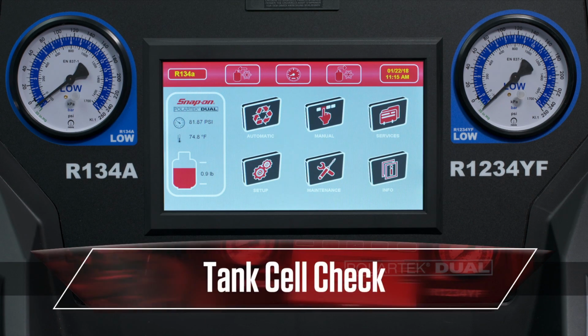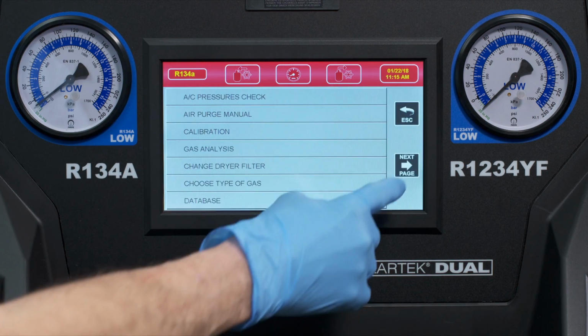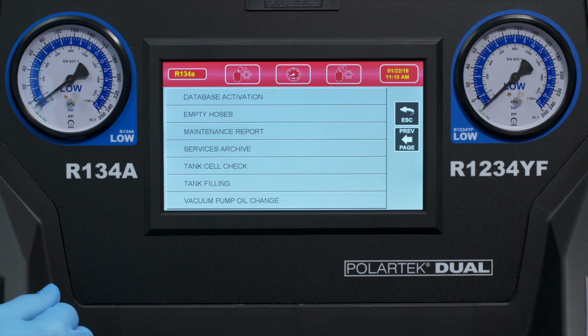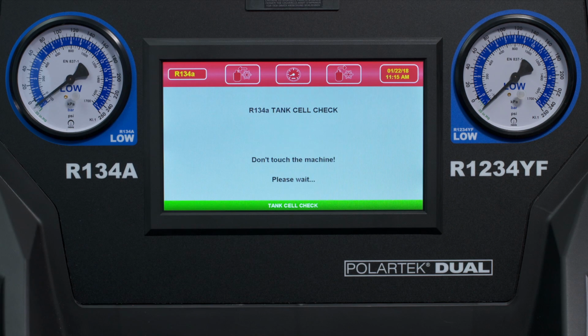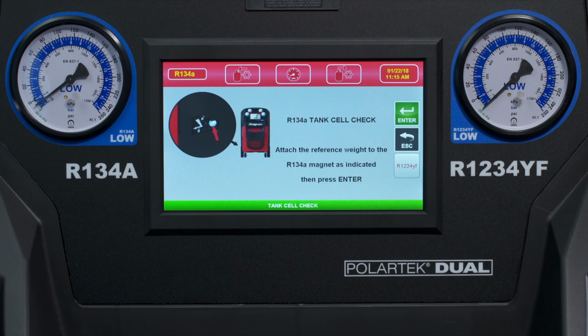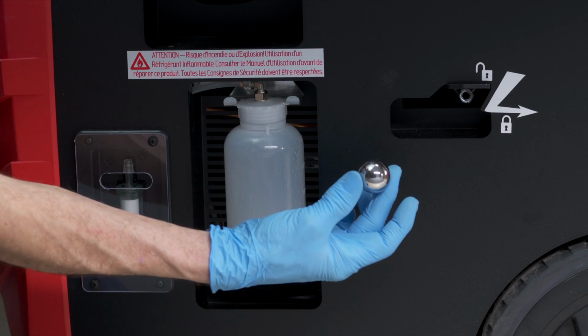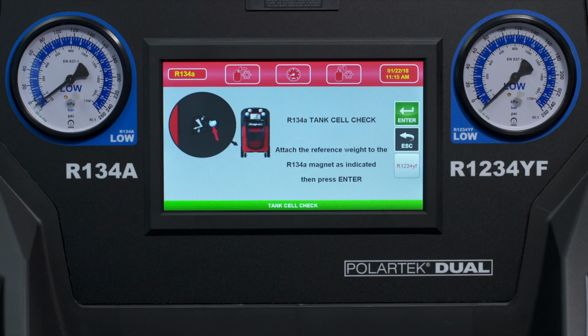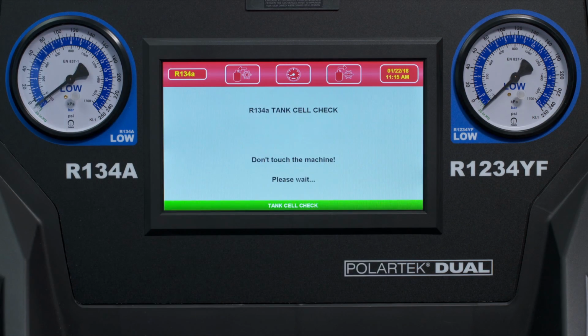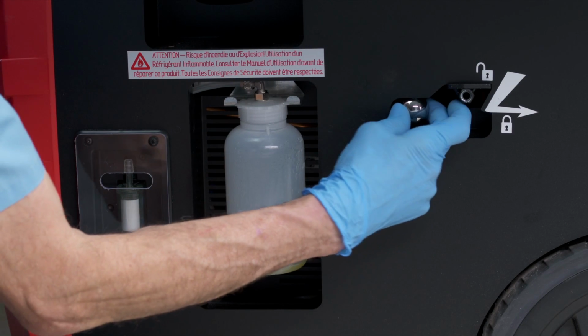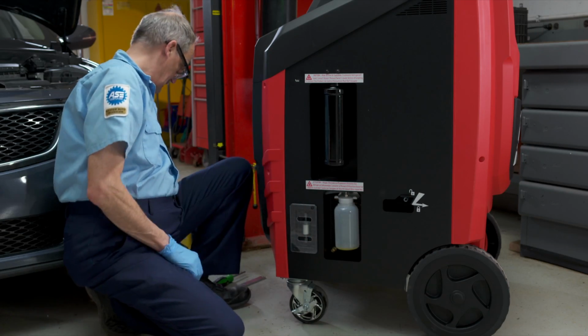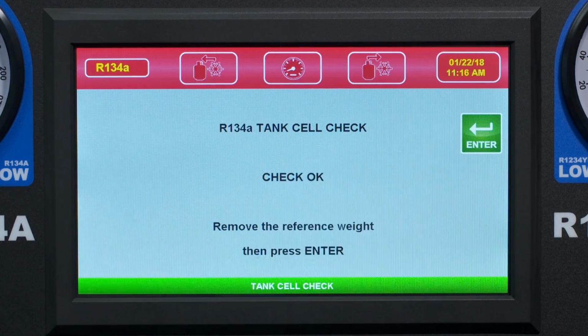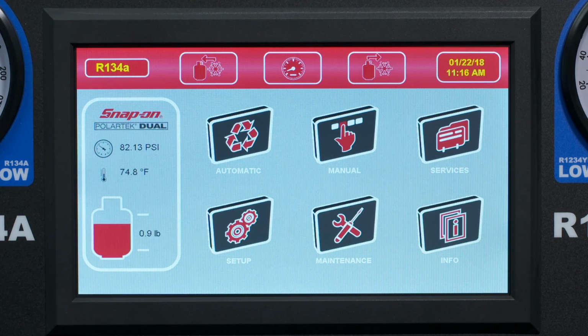To check the calibration of your machine, perform a tank cell check. From the main screen, select Maintenance, Next Page, and then Tank Cell Check. At this point, the machine will prompt you to attach the calibration ball provided with the machine. Then press Enter. The machine will verify calibration and prompt you to remove the calibration ball. Press Enter to complete the process and return to the main screen.